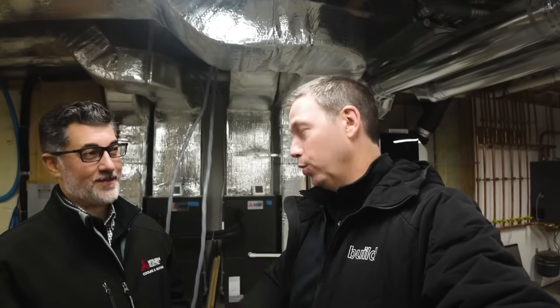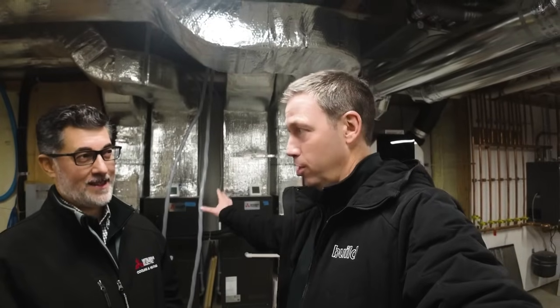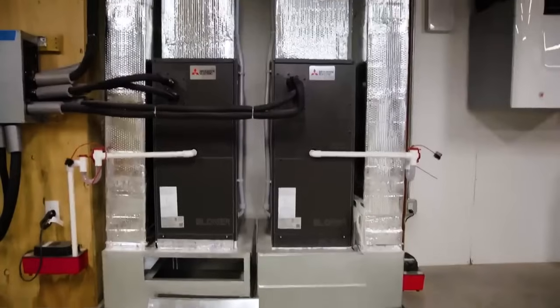Well, I'm going to say that they're thinking back 30 years ago, 20 years ago, even 15 in some cases. That technology's all changed today, and we have the ability now to heat well below zero. So this unit behind me is a 4-ton heat pump unit. In the wintertime, how cold can it be outside and still get 100% heating capacity out of my 4-ton unit?